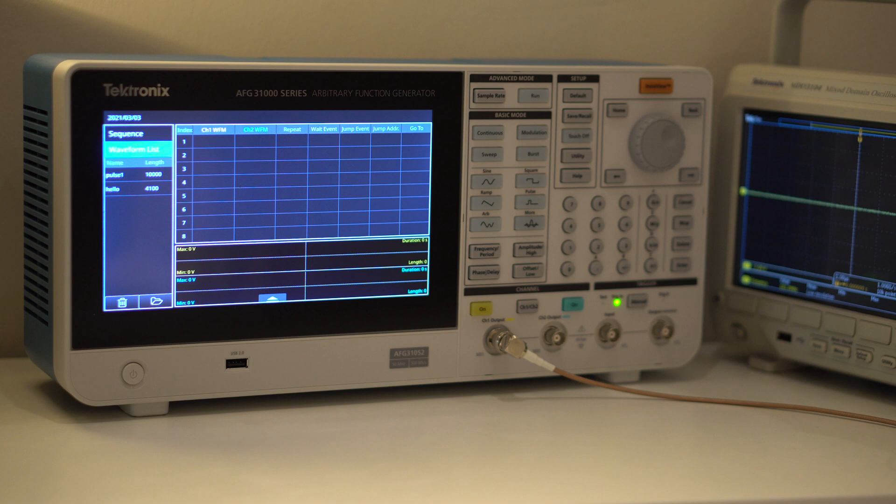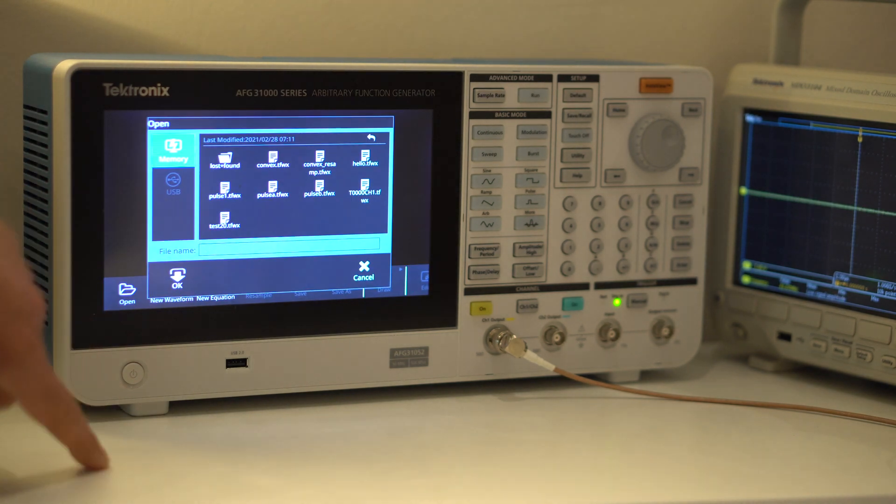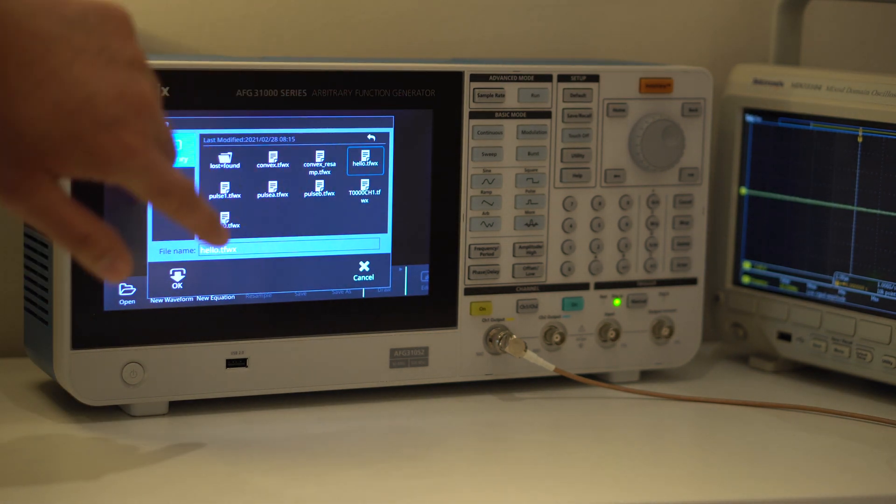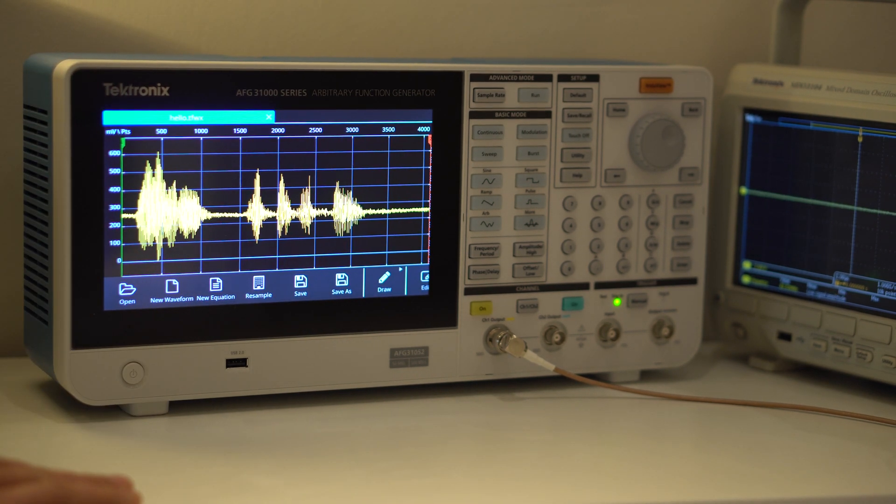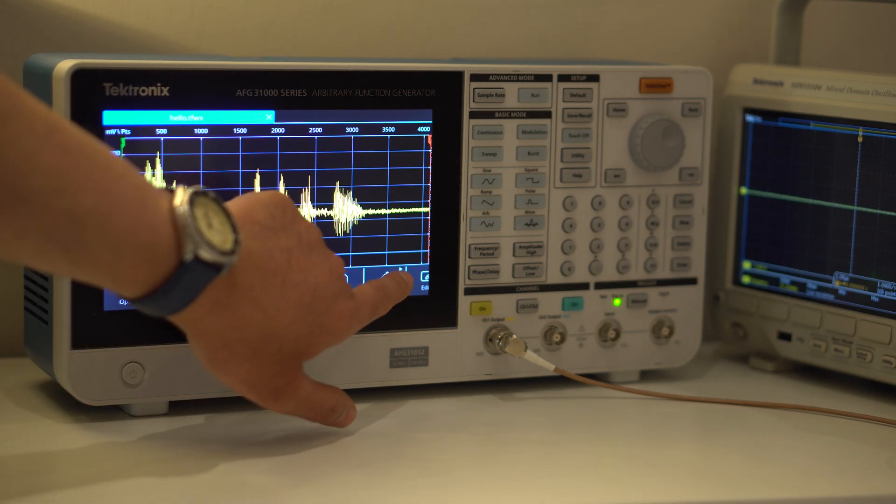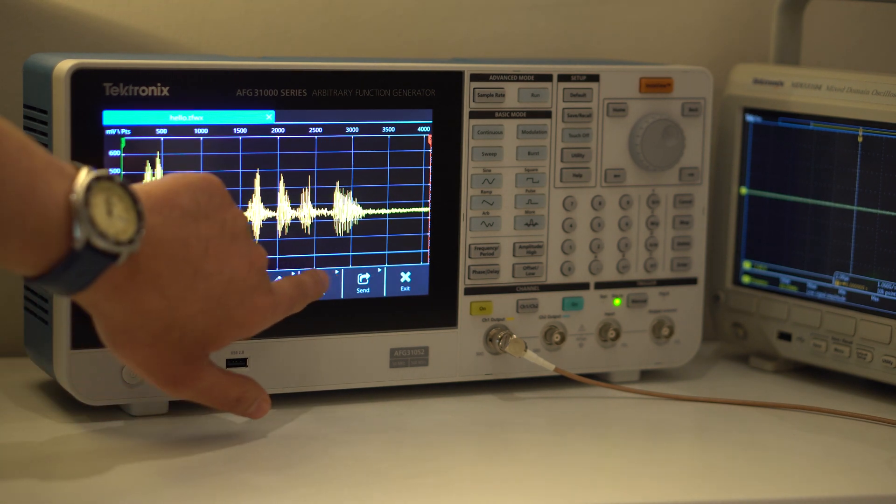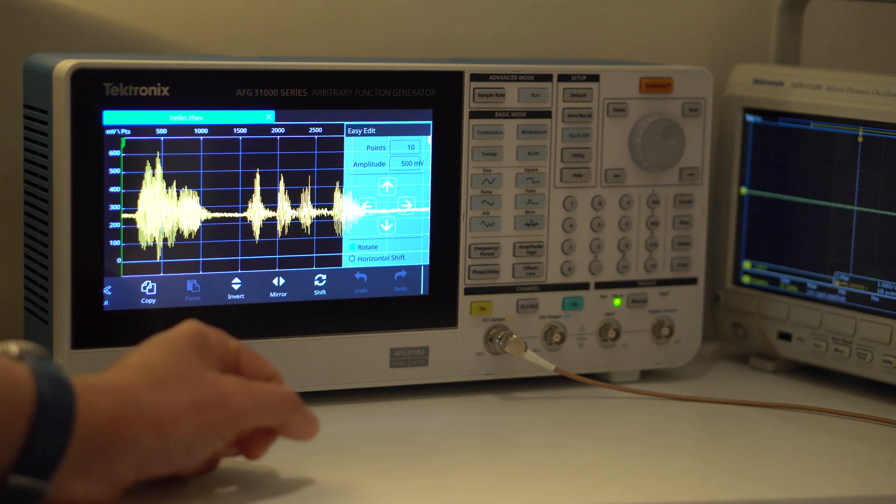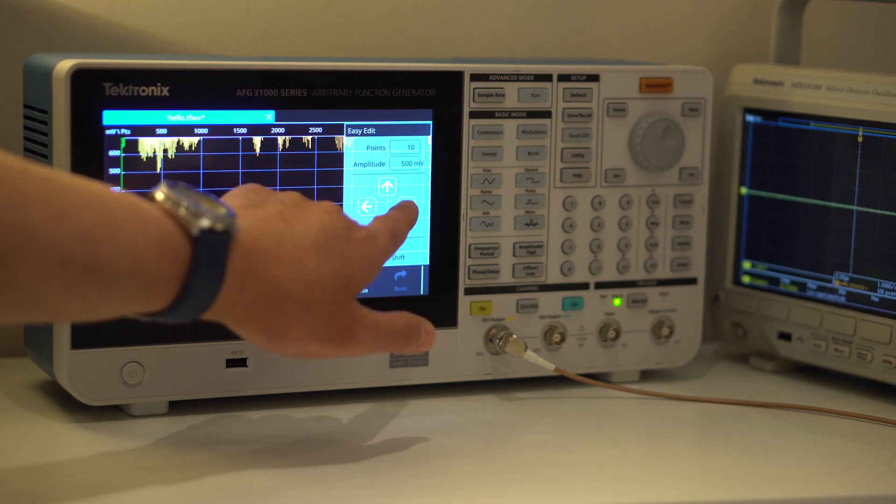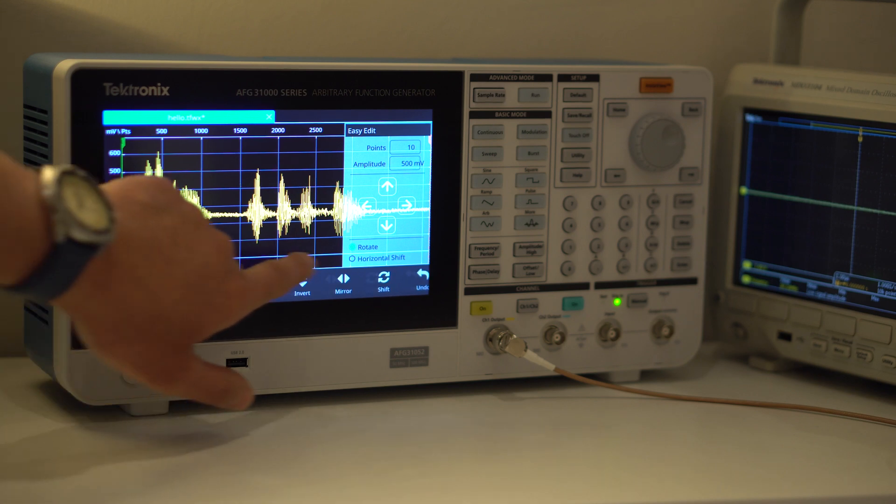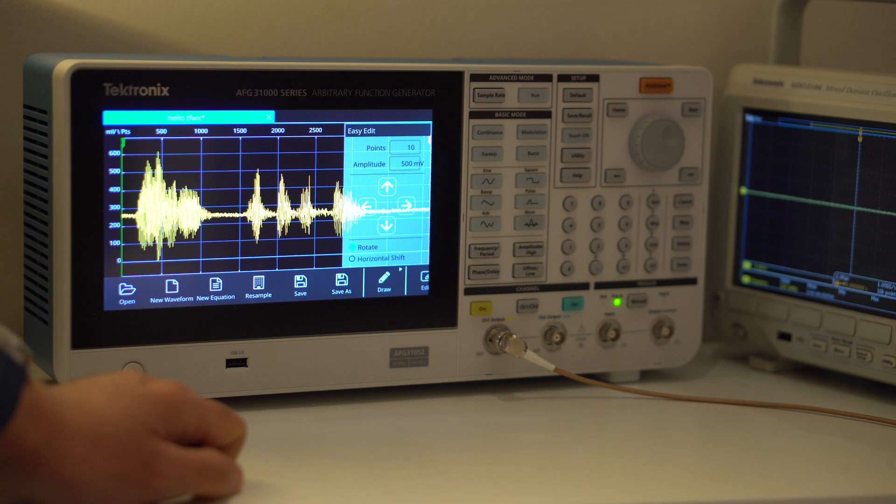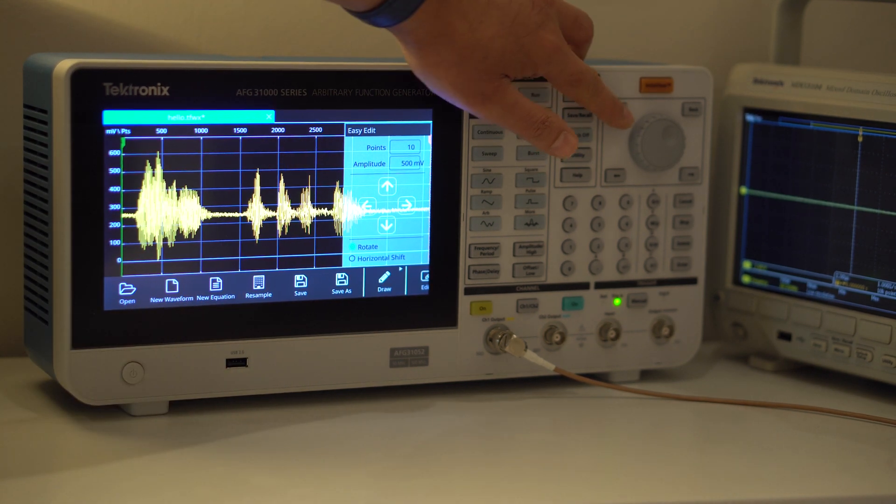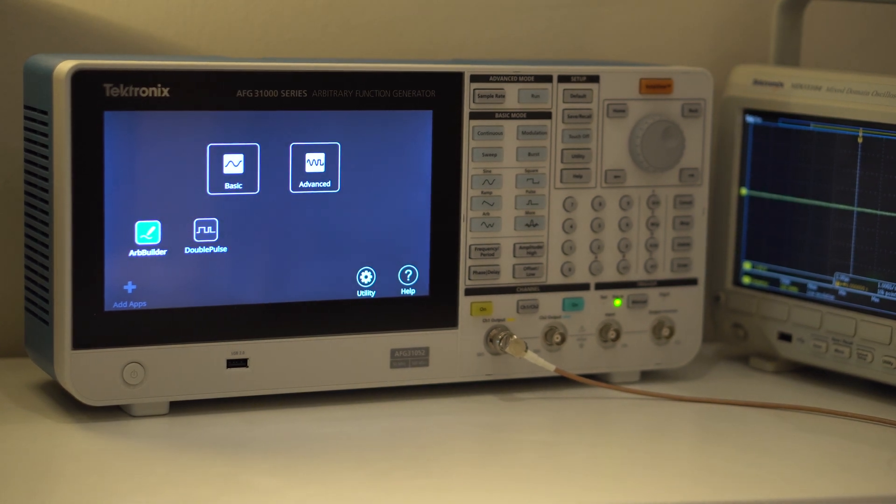Back from the top home menu, the built-in ArbBuilder application capability provides a method to design or manipulate custom waveform files. The example here shows a speech waveform that was stored as a wavefile on a PC, then converted into the Tektronix format, and then transferred across using a USB memory stick into the AFG31K internal file system. There's various things that can be done to manipulate the waveform, or it can all be done on a PC and transferred across. For example, I can shift the waveform by adding an offset, so it's good for making quick adjustments on the fly without needing to keep accessing the PC to create new files. You can actually just directly edit and save them from here.